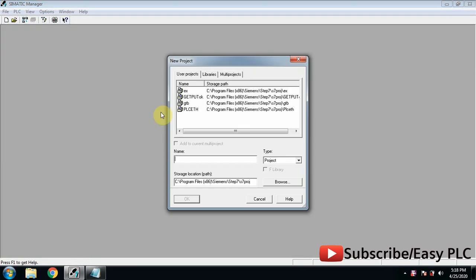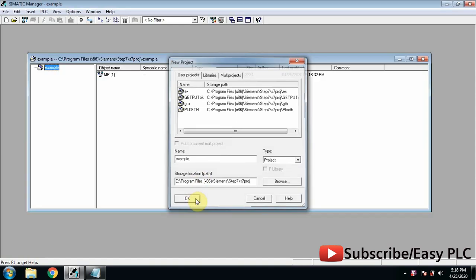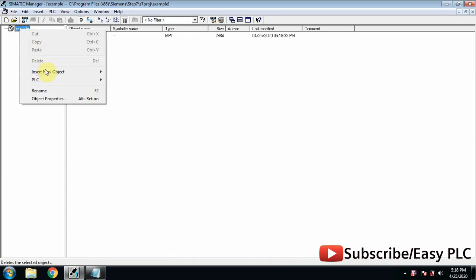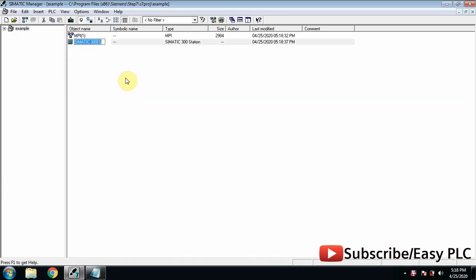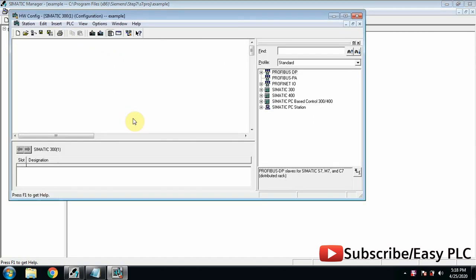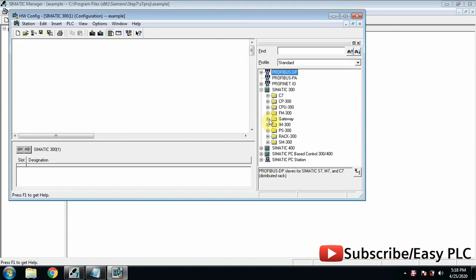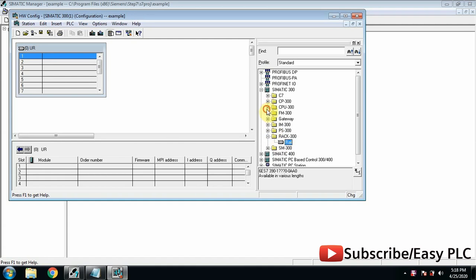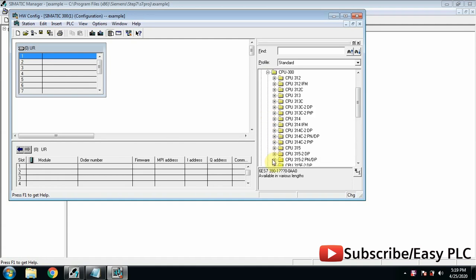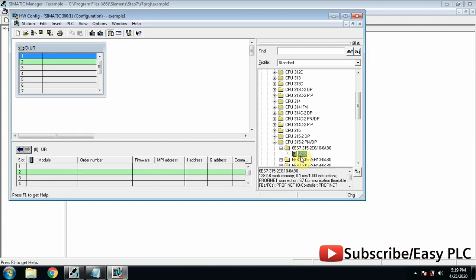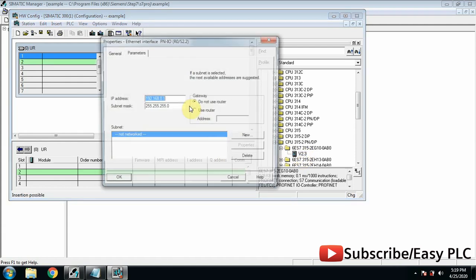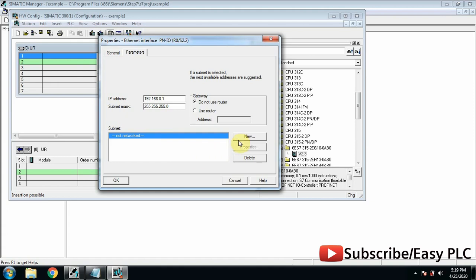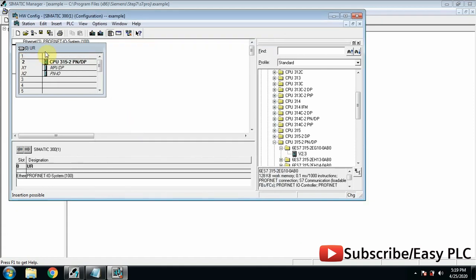First we will make a project and add a local S7-300 station. Now we will go to hardware configuration and add a PLC with PROFINET option, so we can use S7-300 315 PN/DP PLC. We can change the IP address of the PLC if required. Create the Ethernet network and click OK.